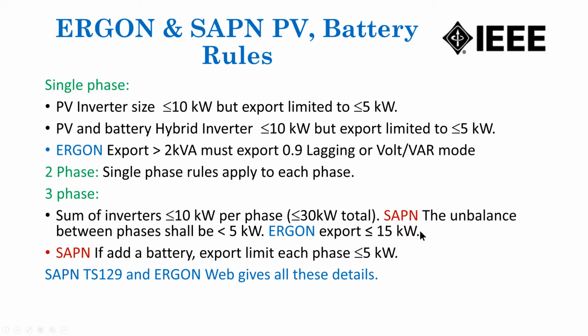In South Australia, the unbalanced load shall be less than 5 kilowatt. In Ergon, you can export up to 15 kilowatt and you're okay. In South Australia, if you add a battery, each phase must be limited to 5 kilowatt.